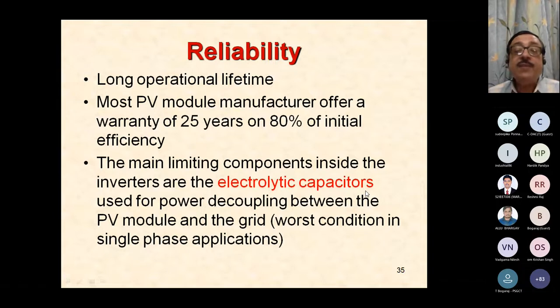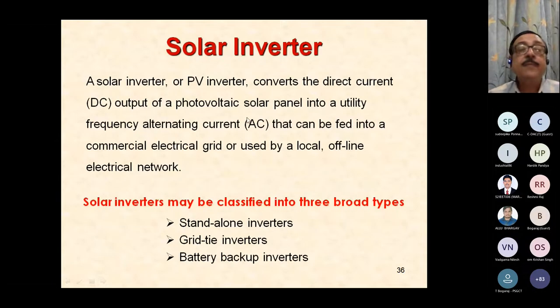Why do we need the electrolytic capacitors? Because they have to absorb the reactive power and the power line ripples, because the reactive power cannot flow back to the DC side. There is no absorption of power on the DC side. So we'll see why the electrolytic capacitor is required and what the flow of reactive power inside the inverters is. We'll take a look at that later.